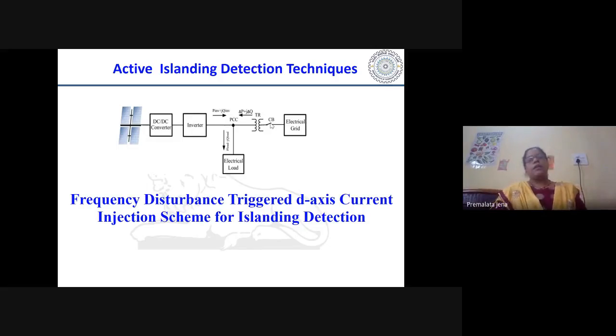But in our case, we do not inject the disturbance signal continuously. If we inject the disturbance 24/7, power quality issues will come again. Even though it's a small disturbance, even when there is no islanding situation, your voltage and frequency will still deviate a little bit.